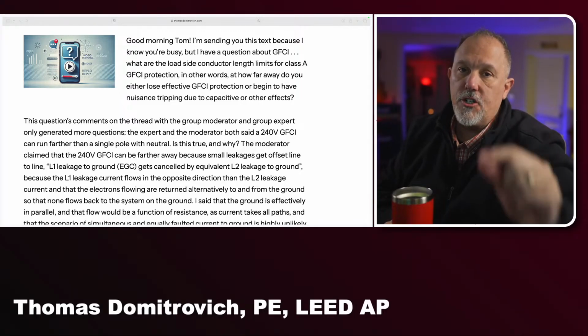Based upon the functionality, think about what a GFCI is. A ground fault circuit interrupter: the gazaltas have to equal the gazintas. Whatever goes out the hot has to come back the neutral. And if I have two hots and no neutral, remember that it's AC current, so it's going both ways on those two conductors. Any current that goes outside of the normal path, if it exceeds the 4 to 6 milliamps, it's going to open. It's an unforgiving technology. It doesn't care where it's going.